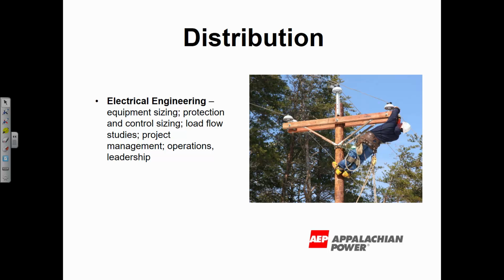So generally if we have a fault, like a tree on the line, or a bird or a squirrel, you want the protection and control device immediately upstream from that fault to trip. That way when our line guys go out to patrol the line to determine the reason for the outage, they'll know when they see a recloser tripped that they just need to look immediately past it to find the cause.